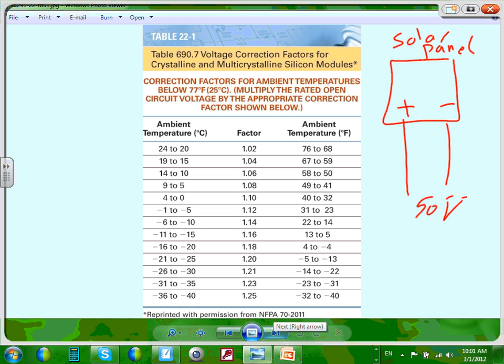And I need to put it in Minnesota, and the ambient temperature could be, in our great state of Minnesota, we could land probably easily in this area here at one time, right? Easily minus 24 to 25 in the winter, we can land on this. So look what happened. If you land it here, then look what you need to do with your open voltage. You need to increase the voltage to 1.2.